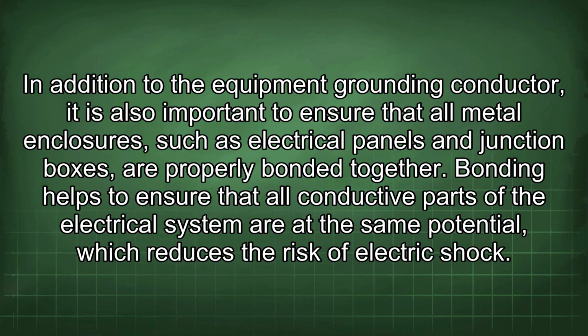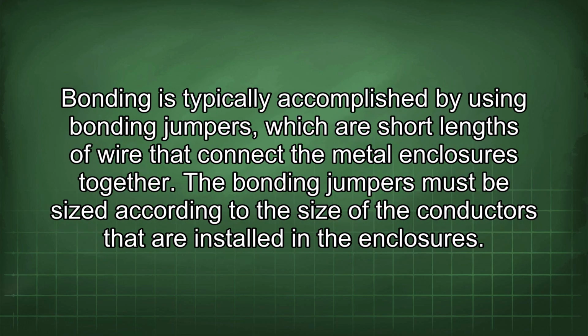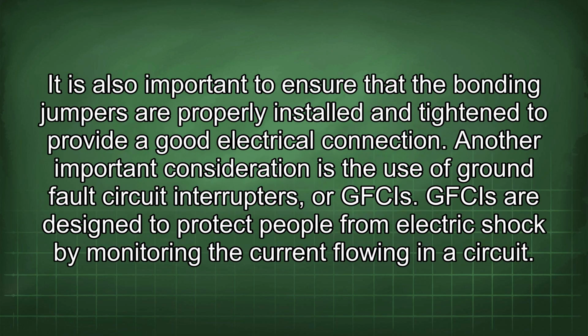In addition to the equipment grounding conductor, it is also important to ensure that all metal enclosures, such as electrical panels and junction boxes, are properly bonded together. Bonding helps to ensure that all conductive parts of the electrical system are at the same potential, which reduces the risk of electric shock. Bonding is typically accomplished by using bonding jumpers, which are short lengths of wire that connect the metal enclosures together. The bonding jumpers must be sized according to the size of the conductors that are installed in the enclosures. It is also important to ensure that the bonding jumpers are properly installed and tightened to provide a good electrical connection.